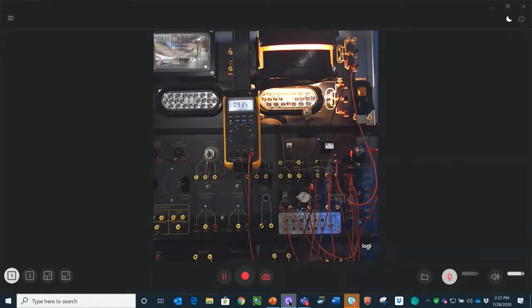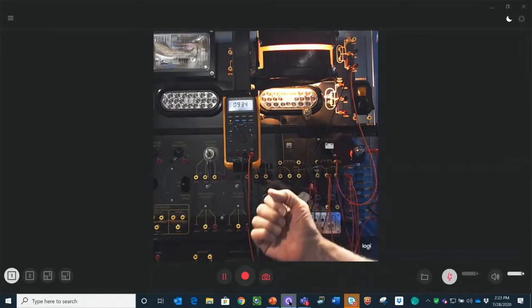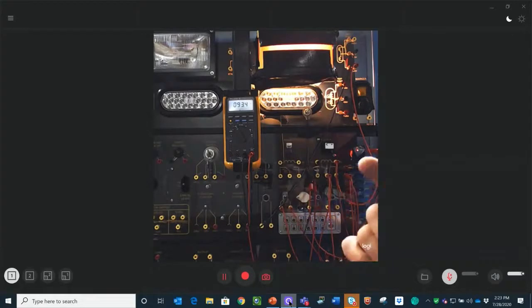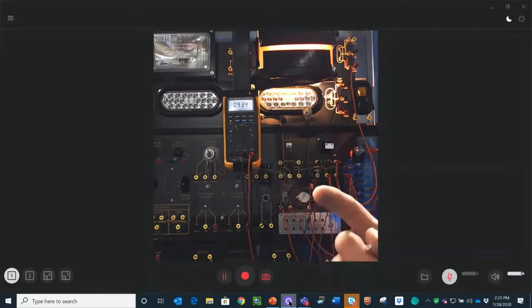Now we know from our experience in the past, we don't want any more than 200 millivolts across, voltage drop testing, before there's a high resistance problem. So we're still good. But my point is, when you're doing this on the bench, make sure that the load you're putting through the relay matches the load in the circuit. How do you do that?